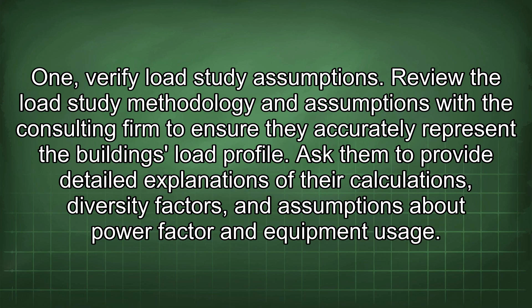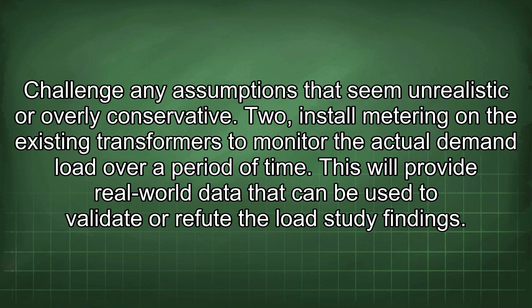2. Install metering on the existing transformers to monitor the actual demand load over a period of time. This will provide real-world data that can be used to validate or refute the load study findings. Use the metering data to identify peak demand periods, load patterns, and any unusual energy consumption trends.